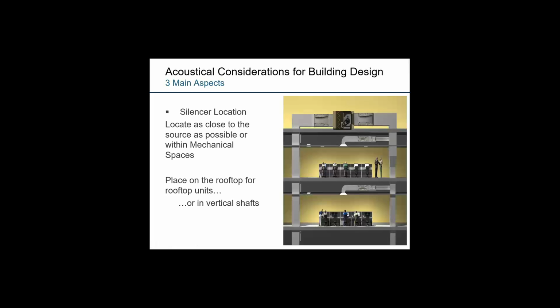The location of silencers is also something to consider, and silencers are often installed as close to the source as possible while still allowing for appropriate inlet and outlet conditions. And what I mean by that is that when a silencer is installed in close proximity to an air moving device, there can be things that need to be considered, like system effects.